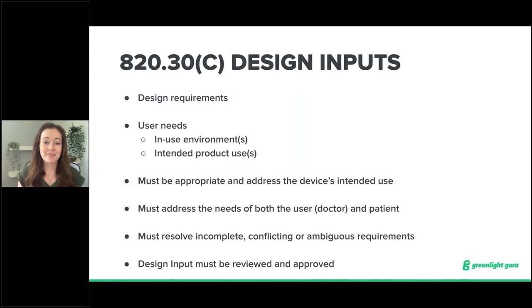Design inputs are truly the starting point for product design. The requirements forming the design input establish a basis for performing subsequent design tasks and validating the design. Developing a solid foundation of requirements is the single most important design control activity. Design input requirements fall under three categories. First, functional requirements: specifying what the device does, focusing on operational capabilities. Second, performance requirements: specifying how much or how well the device must perform, addressing issues such as speed, strength, response time, limits of operation, and quantitative characteristics of the use environment including temperature, shock, and humidity.